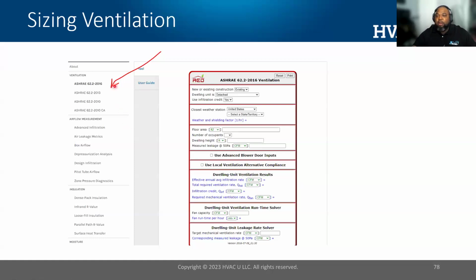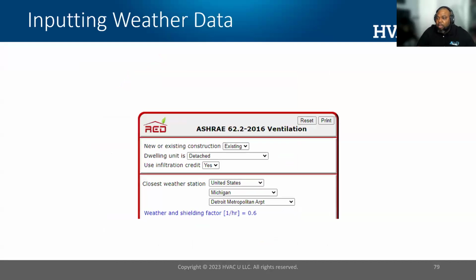When you pull up the tool, looking in the left hand corner here, you have to pick which ASHRAE standard you're going to be using. All right. In this example, we're going to use 2016. And on the right here, these are inputs that you're going to add to come up with the calculations. Based on your inputs, this tool is going to help you size the fan necessary for ventilation. All right, so we'll walk through an example here. On the first part, you have to tell the tool what your building is. Is it new or existing construction? Is it detached, meaning multifamily or single family home? And do you want to use an infiltration credit?